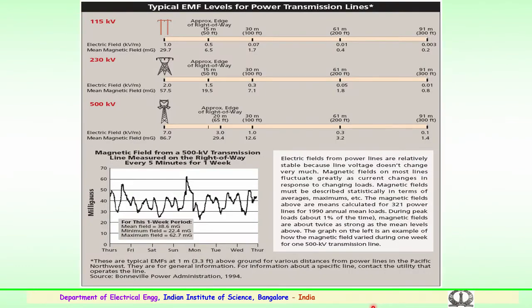Typically when you see the transmission towers, you have both the electric field and the magnetic field in the vicinity of the power transmission lines. Here are a few examples for various voltage levels, 115, 230 and 500 kilovolts. You see the towers and the distance from the towers, with the electric field in kV per meter and the magnetic field in milligauss. The values are clearly given here.